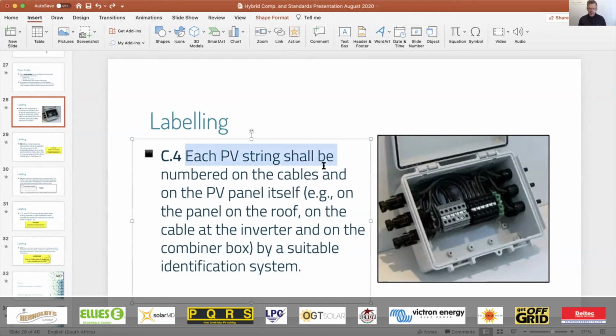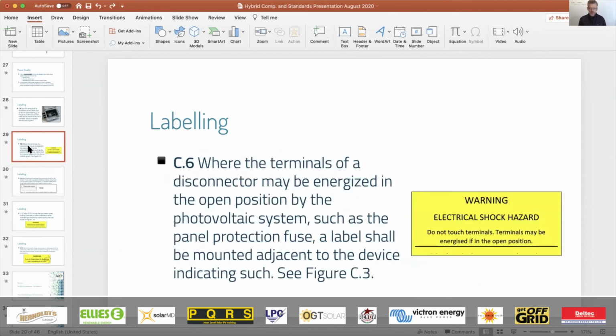So each PV string shall be numbered on the cables and on the panel. And then it goes further to say, for example, on the panel on the roof, on the cable at the inverter, and on the combiner box by a suitable identification system. So if you do an installation and you get hit by a bus, you want to be able to leave your installation in such a way that someone else knows what's going on in your installation. Of course, those labelings would possibly coincide with the labeling in the line diagrams and the drawings that you've left in the DB board.